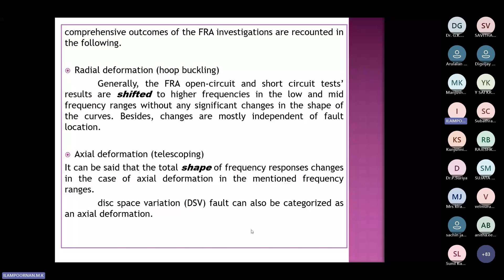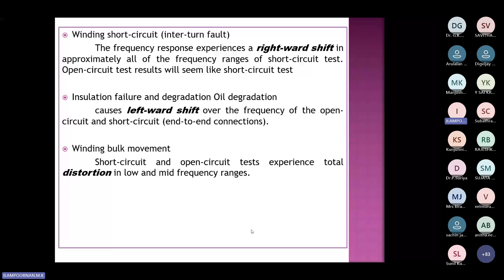So different things. Radial means it will be shifting. Axial means the total shape will be changing, and you will have a rightward shift when the winding is short circuited. If it is an insulation failure, there will be a leftward shift. If there is a bulk movement, there will be total distortion in the low and mid frequency ranges.